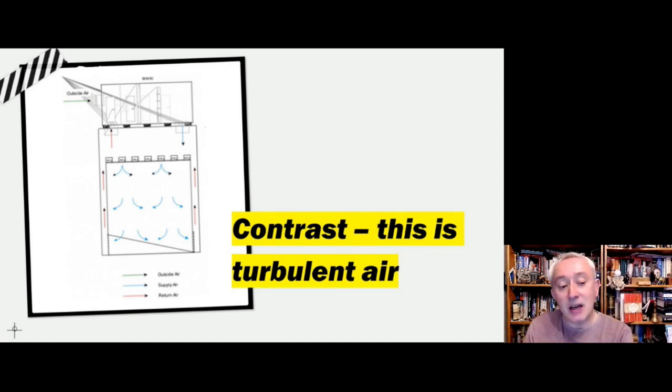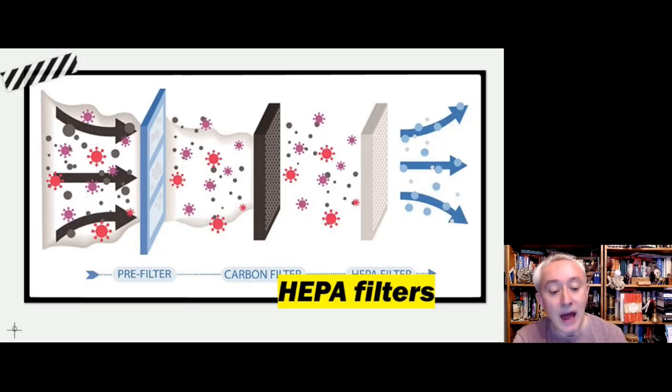So this is great for maintaining contamination control where there's people in the surrounding room, but within the aseptic core, within the grade A or ISO class 5 area, we want to achieve unidirectional airflow, and this is provided through HEPA filters.